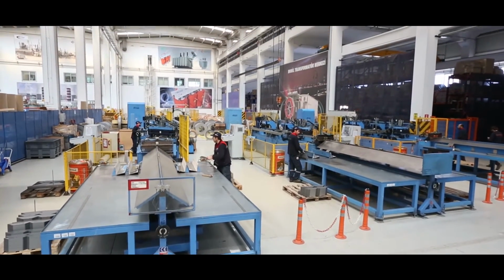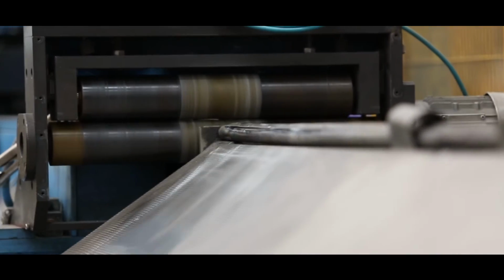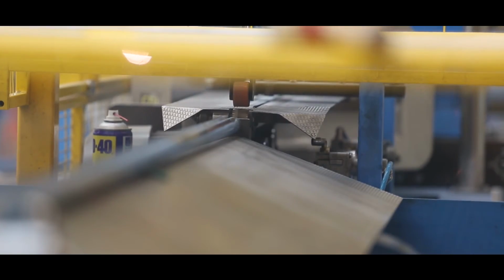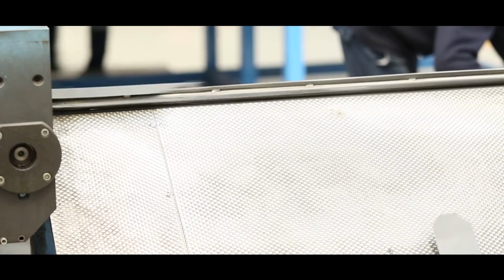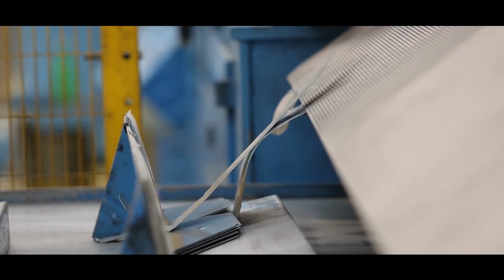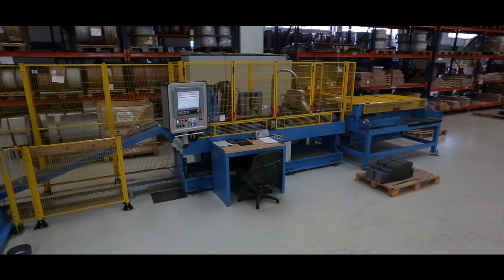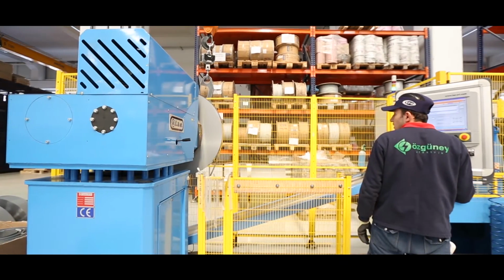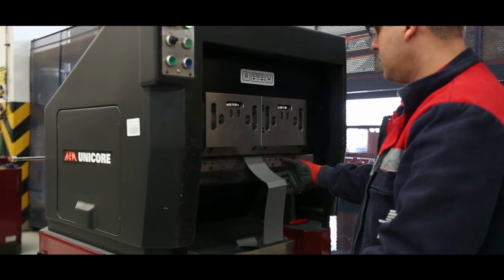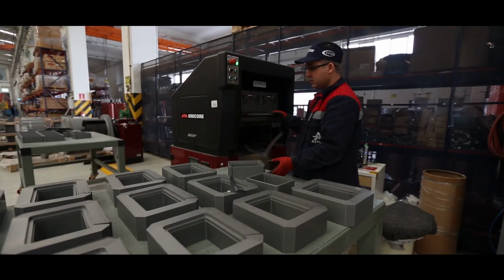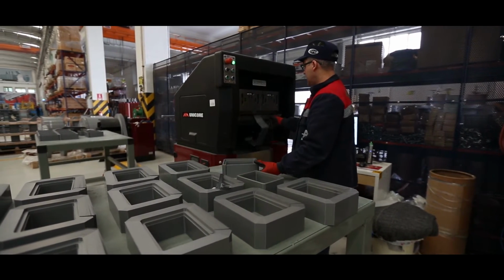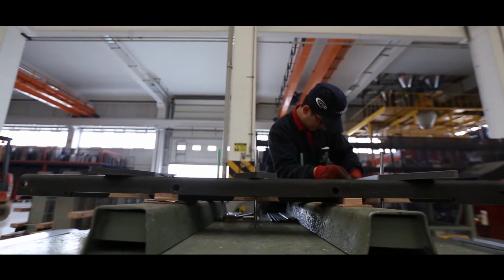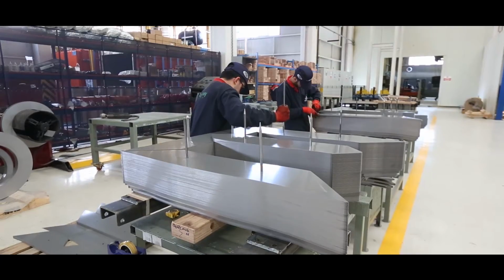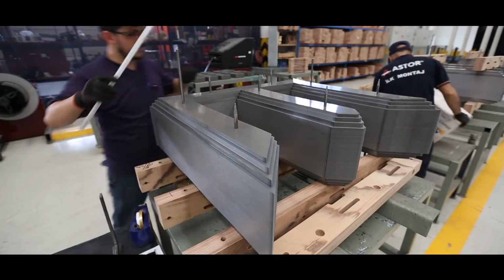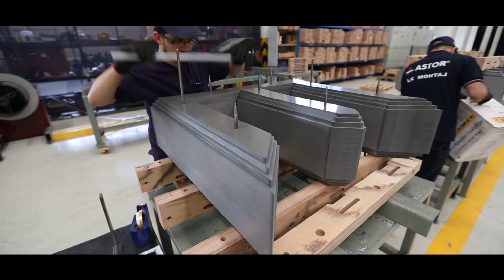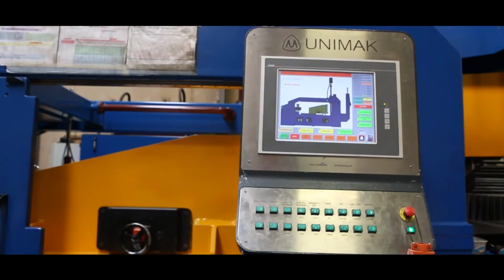The core is manufactured from M5, M4 silicon alloy sheets with oriented crystals and a thickness of 0.30, 0.27 and 0.23 millimeters. Sheets with 45 degrees slanted cut at the transition regions of the magnetic circuit. The production of the core is performed according to the project by cutting all of the sheets utilized within the magnetic circuit with CNC-controlled cutting machines. The cutting and alignment of the magnetic circuit is performed with a method called step lap, which is useful for minimizing the iron loss. The nucleus is aligned with cross and longitudinal step lap implementation.